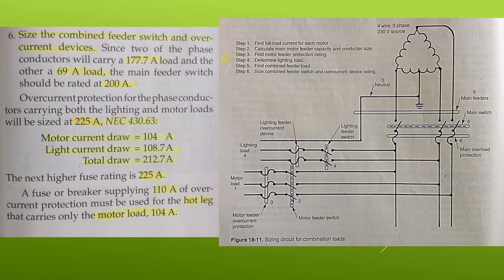A fuse or breaker supplying 110 amps of overcurrent protection must be used for the hot leg that carries only the motor load, 104 amps.